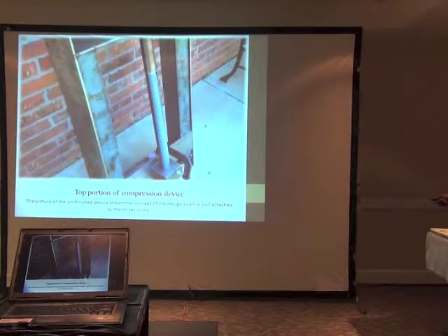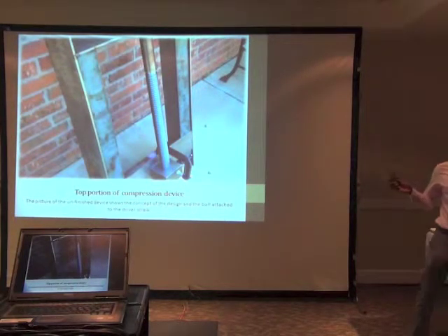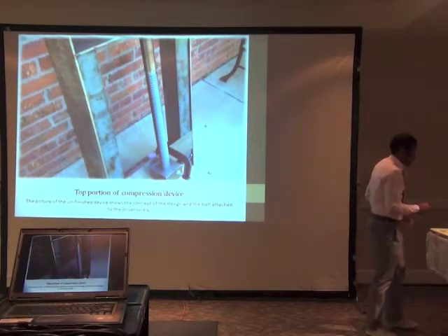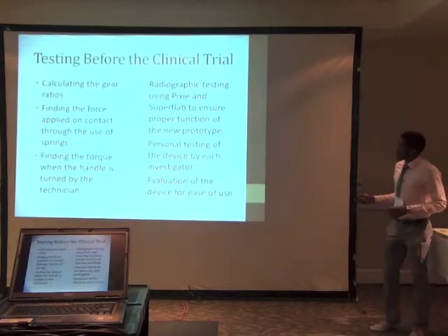So there's going to be one plate, this is the plate I'm talking about, the metal plate, and the bolt is going to be sandwiched in between. And there's going to be another one on this side, and the bolt is going to be sandwiched in between. The threaded shaft is going to be running through the middle of the device. And we're obviously going to block the screw up so you won't see the inside working. So the patients won't be scared seeing all this metal shaft with thread going through. So it'll be blocked up.